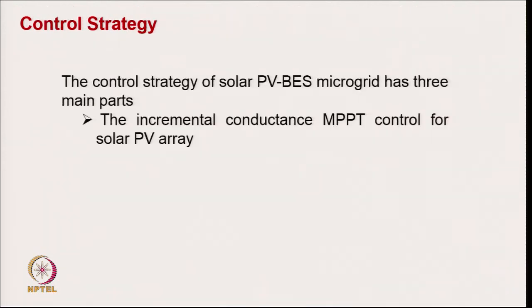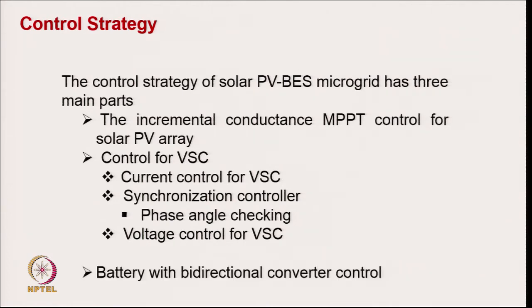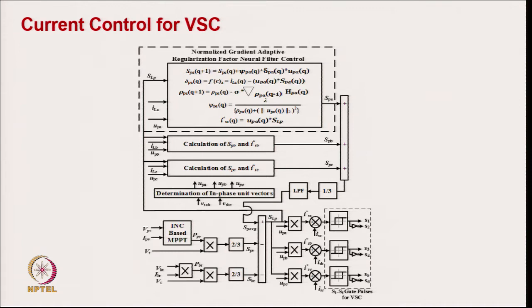The control system has the following parts: maximum power tracking algorithms for maximum power extraction from the solar PV array; control of voltage source converter for current control in grid-connected mode; synchronized controller for grid appearance and disappearance handling islanding and reconnection; you check the phase angle of the point of common coupling voltage as well as the grid voltage and synchronize; and voltage control for islanding operation of the voltage source converter and battery with bi-directional control.